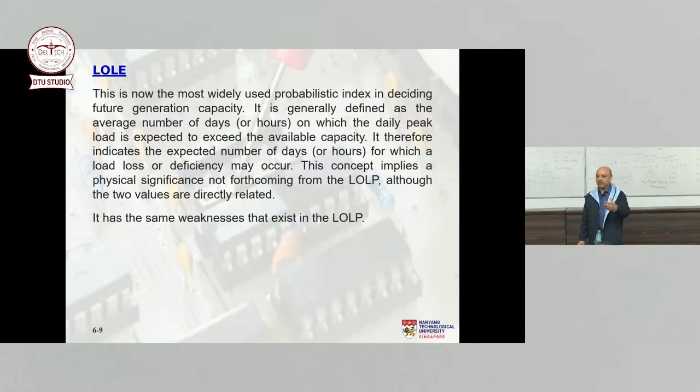And if you of course try to put it in hours, 24 hours in 10 years, 2.4 hours in 1 year. Yeah, 2.4 hours. Of course it doesn't tell you whether I'm going to lose 2.4 hours on 31st of December or whether I'm going to lose 0.1 hours in January, 0.2 hours in February. So it could be, right? We know nothing like that. We don't know the frequency. We don't know the duration. All we know is how many hours per year are we not going to get supply. Is it enough for us? Well, doesn't matter. It is the most popular index at the present time.